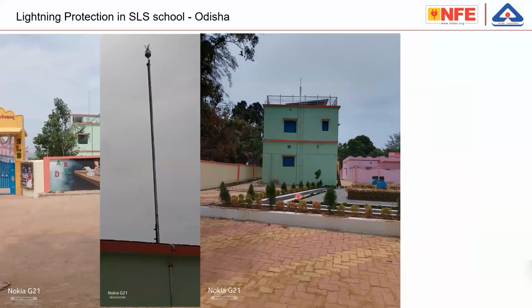Whereas in this particular building, a lightning protection system as per a story is installed, not as per a standard, but as per a story. With one down conductor here, probably you should keep 10 meters away. As with the tree, you must keep 10 meters away from this particular conductor, otherwise it is going to create a real hazard.